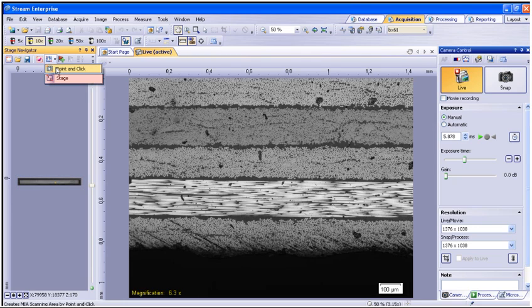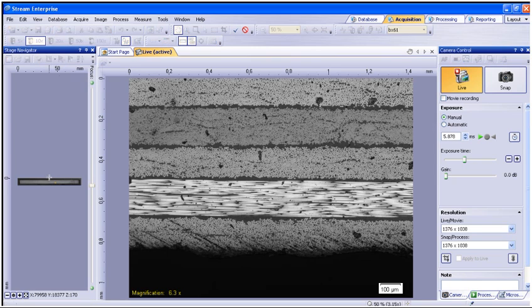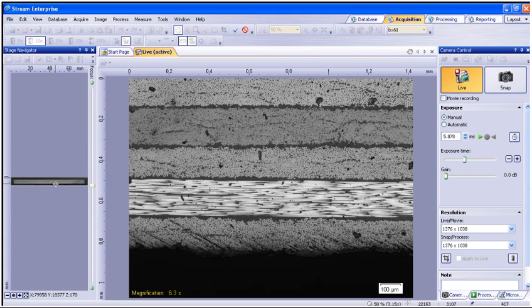The second is to physically drive the stage to two opposing points to define the area. For this example, choose point-and-click. After you select point-and-click, you will have to zoom into the overview image by using the scroll wheel on the mouse. This will allow you to mark the area of interest with more precision.